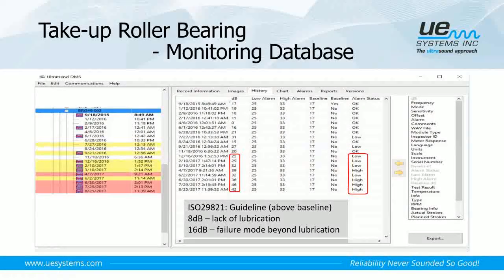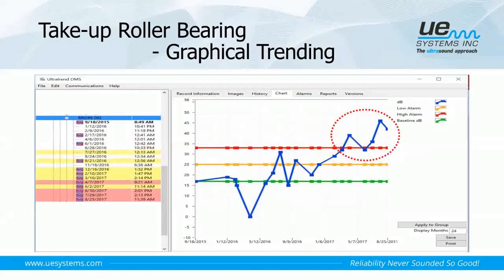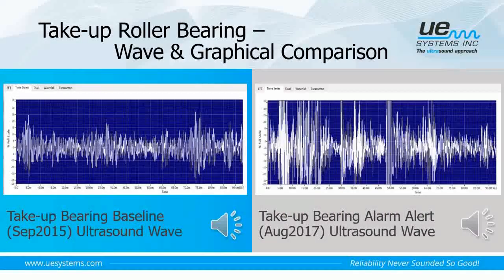The bearing was hitting the alarm level continuously starting in December 2016. We can see the numbers and look at the alarm status. We can also have a better view in graphical displays. And we make a noise quality comparison between the baseline and the alarm level. This is the baseline.